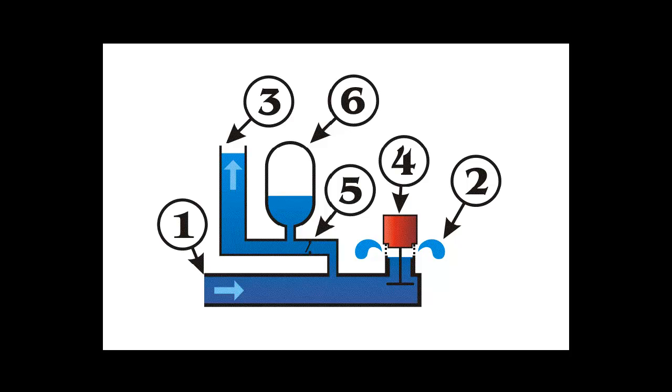The momentum of the water flow in the supply pipe against the now closed waste valve causes a water hammer that raises the pressure in the pump, opens the delivery valve 5, and forces some water to flow into the delivery pipe 3. Because this water is being forced uphill through the delivery pipe farther than it is falling downhill from the source, the flow slows. When the flow reverses, the delivery check valve closes.